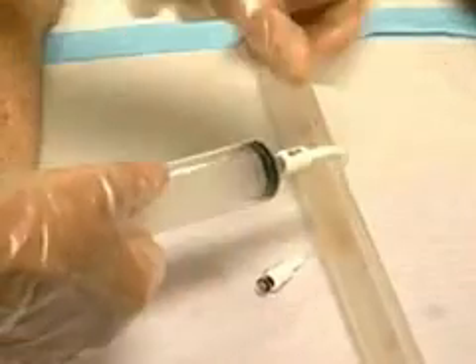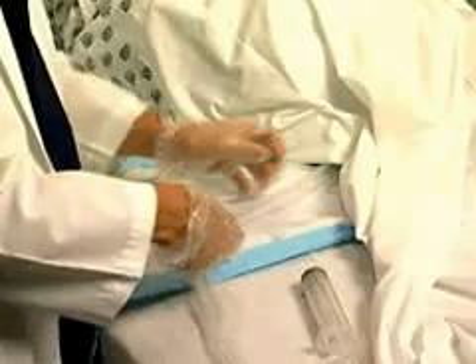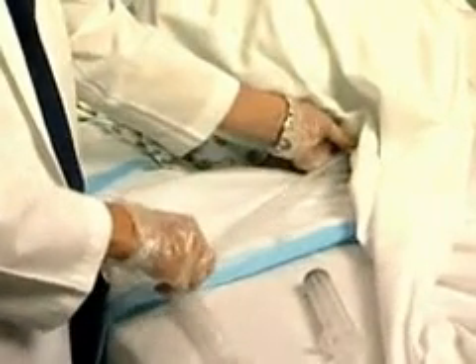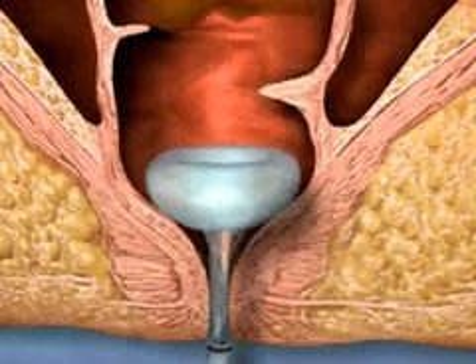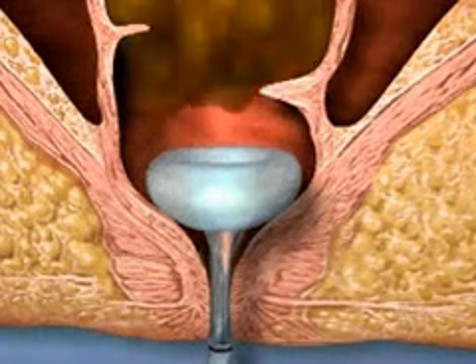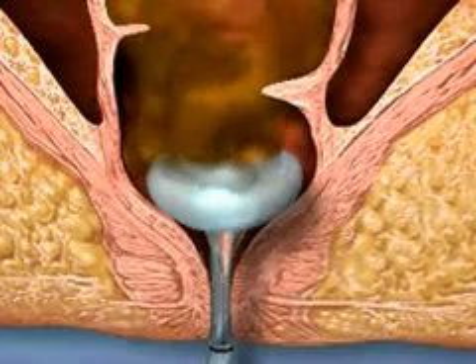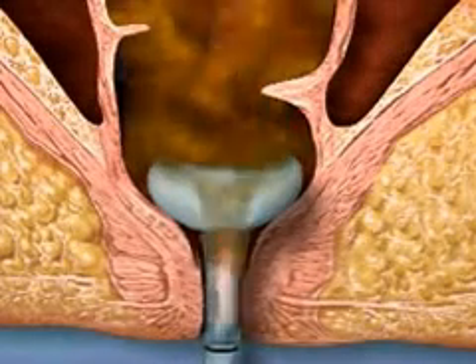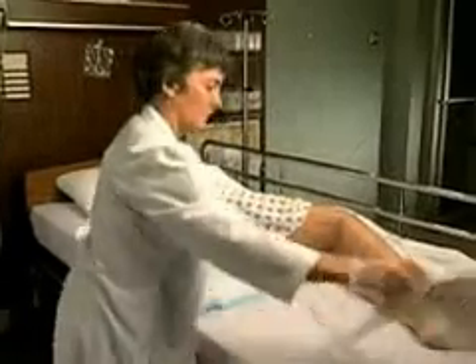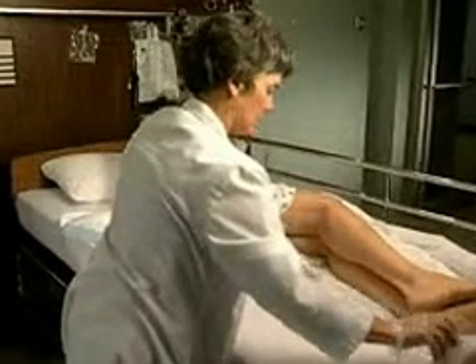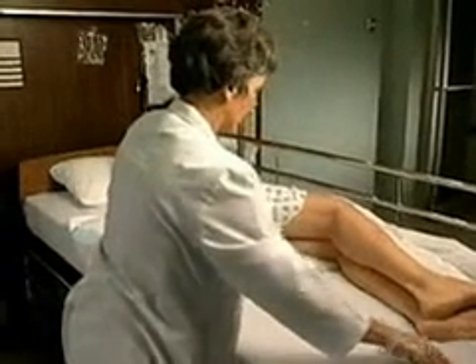Next, remove the syringe from the inflation port and gently pull on the catheter to ensure that the balloon is properly positioned. This will also ensure that the stool will flow into the catheter instead of around it. Then position the length of the flexible silicone catheter along the patient's leg, avoiding kinks and obstruction.